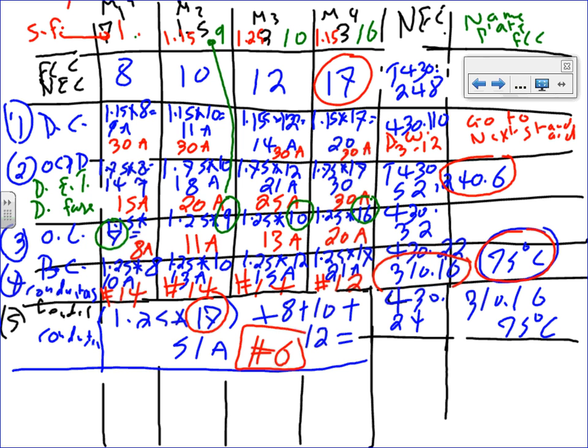Okay, here's my question for you. How many conductors of this number 6 do you need? It's single phase 240. What do you need? 2 conductors. Do I need a neutral? No, unless they tell you otherwise. 3 phase and single phase motors, guys, you don't need a neutral for them. If it's 240, you don't need a neutral, unless they tell you that you need a neutral.